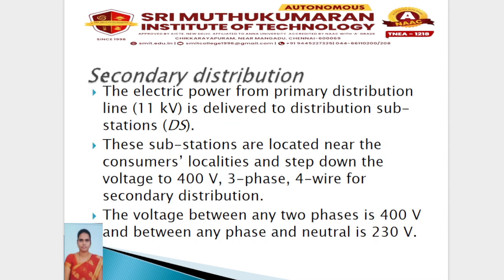Next, secondary distribution. At the distribution substation, voltage is stepped down from 11 kV to 400 volt using distribution transformer. This is a three-phase, four-wire system. Phase-to-phase voltage is 400 volt, phase-to-neutral voltage is 230 volt. This stage is called secondary distribution and it directly supplies consumers.